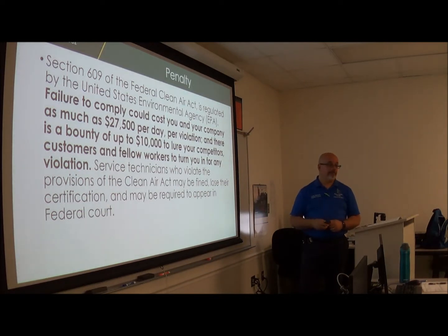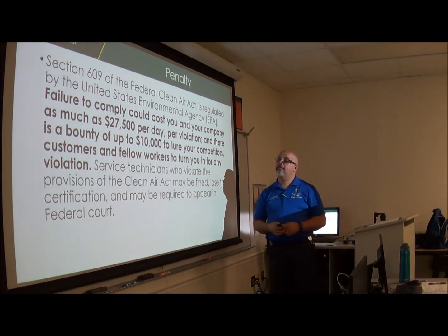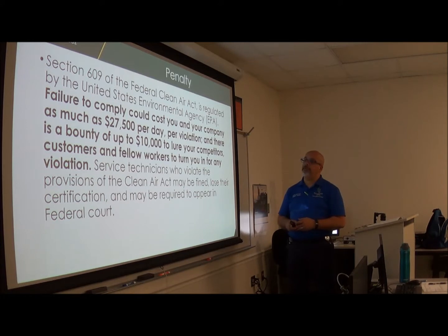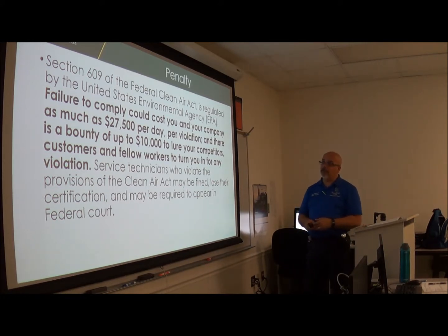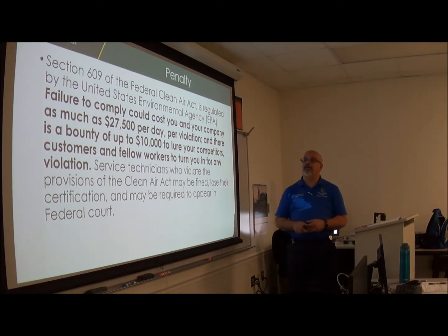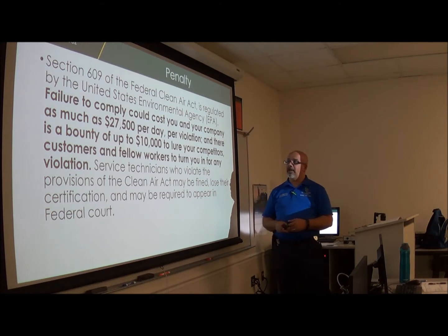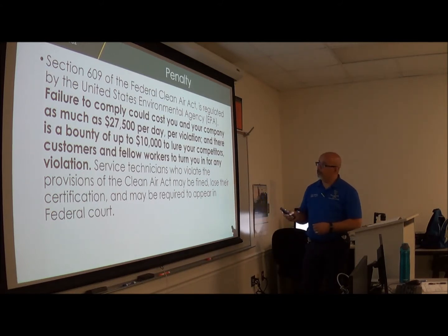The penalty, this is the fun part. Section 609 of the Federal Clean Air Act is regulated by the United States Environmental Protection Agency, EPA. Failure to comply could cost you and your company as much as $27,500 per day per violation, and there is a bounty of up to $10,000 to lure your competitors, customers, and fellow workers to turn you in for any violation.